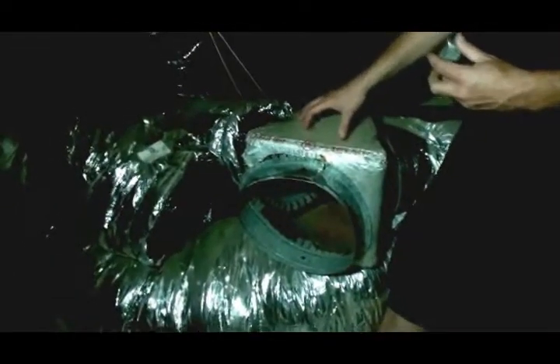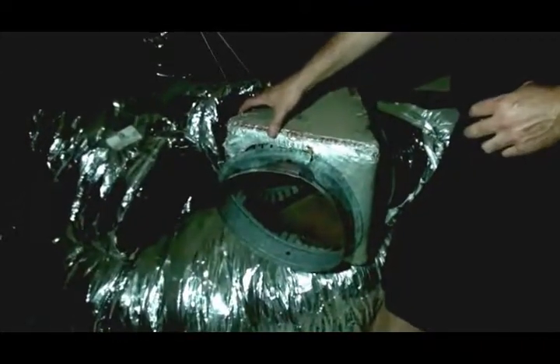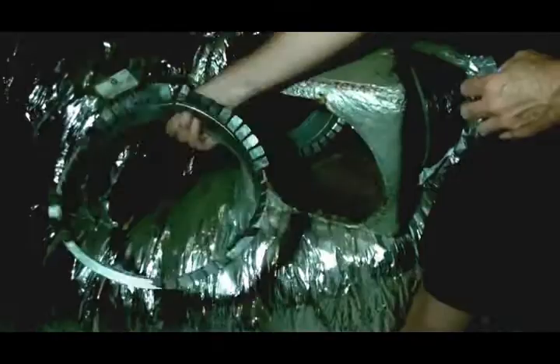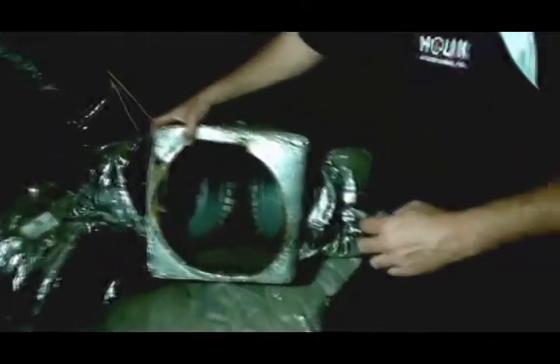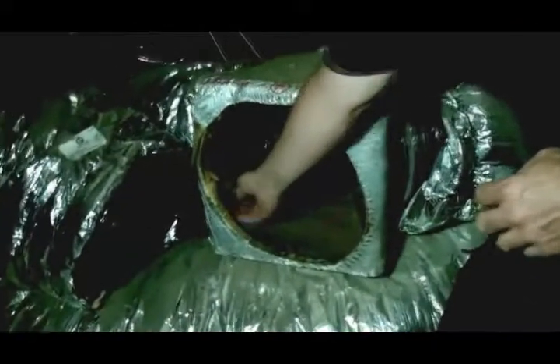Okay, here we are in a smaller part of the attic, and this is something that we here at Houk Air Conditioning will do on each and every job, and we go through your duct system to make sure that connections and distribution boxes like this one here, which is called the ductboard triangle, are removed out of the system. This is a very inefficient way of distributing airflow. They leak. You can see that piece just comes right out, and it's very dirty and dusty inside there. There's a lot of leakage that goes on here.